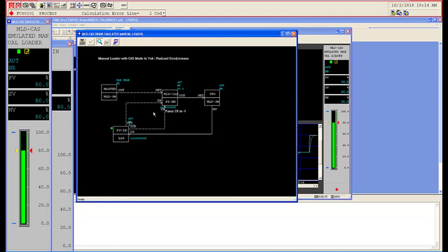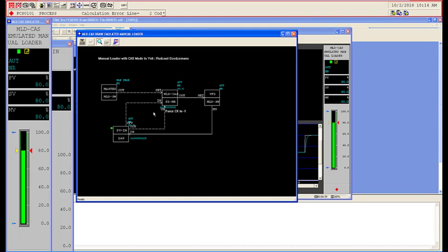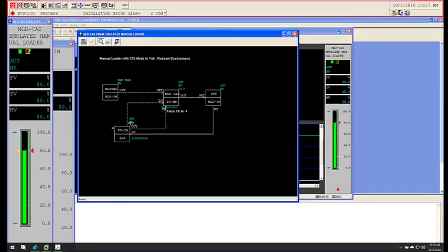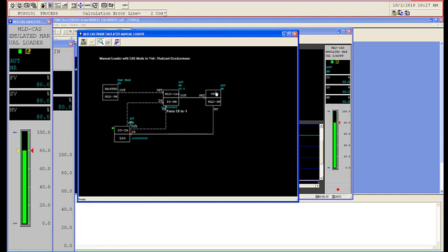This PV is simulated, so it's not going to try and track the set points. Even though there's an integral value here, that's used for something else in the PDMR block. It's important to read the PDMR block. All I'm showing is a sneaky way to do a manual loader where there is a PV, the three modes auto, manual, cascade, where auto really is basically manual where the SV and the MV move together. That resolved our problem for that layer of abstraction.